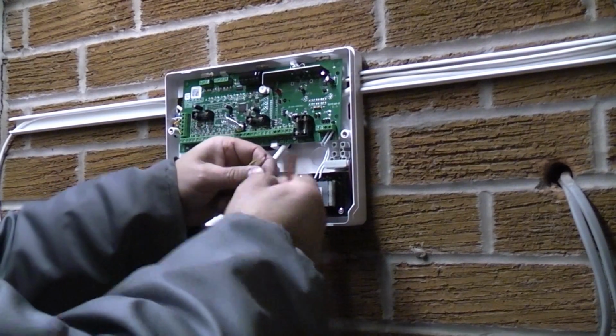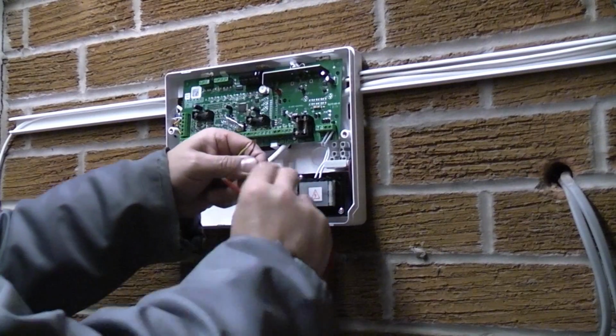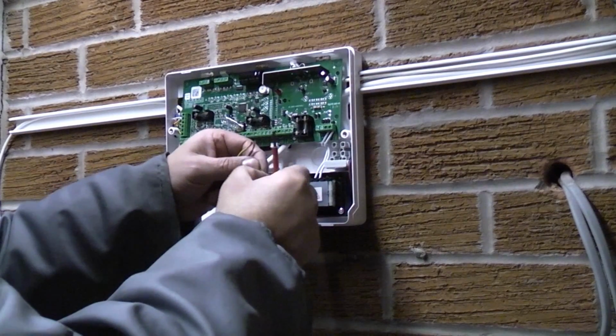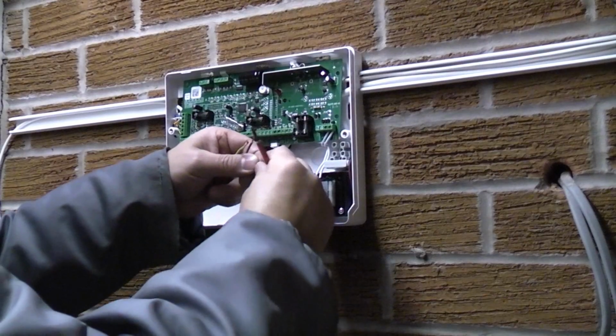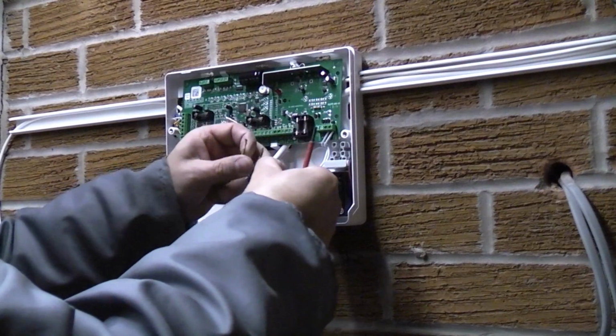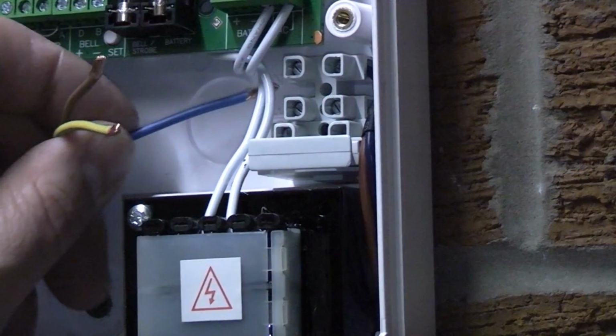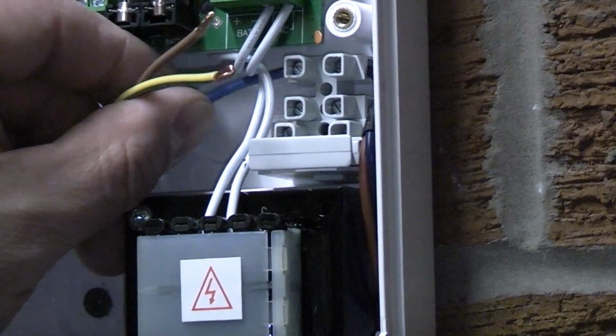So we're going to do the same as what we've done with all the other wires. We're going to twist all the strands together and then fold the conductor back on itself. That will give the terminal something good to grip. We're going to start off by putting the neutral wire into the terminal. Then we're going to tighten the terminal screw.